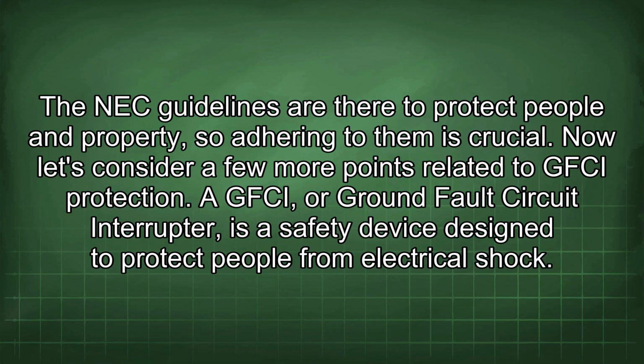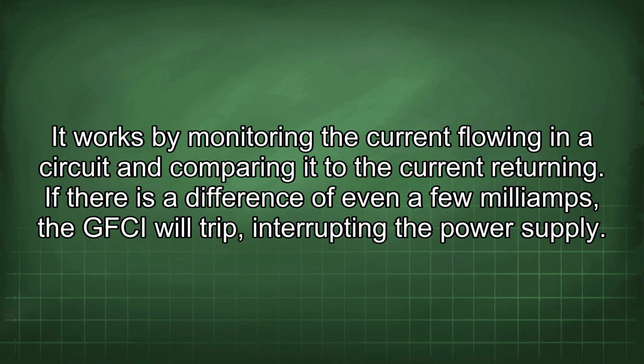A GFCI, a ground fault circuit interrupter, is a safety device designed to protect people from electrical shock. It works by monitoring the current flowing in a circuit and comparing it to the current returning. If there is a difference of even a few milliamps, the GFCI will trip, interrupting the power supply.